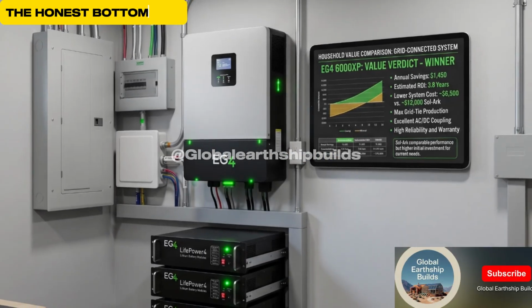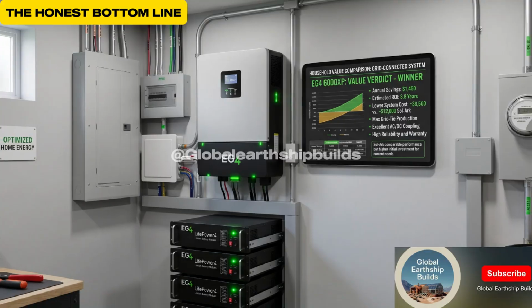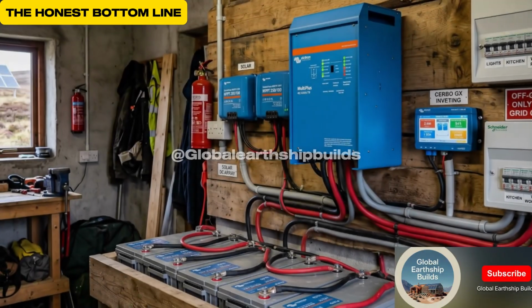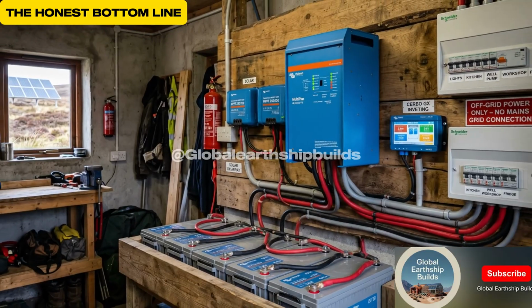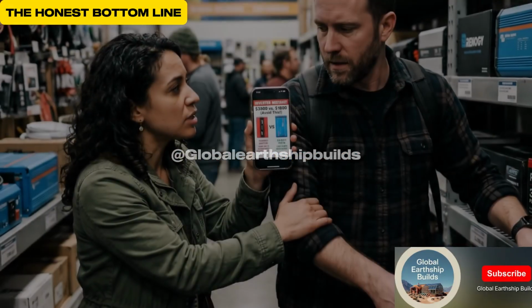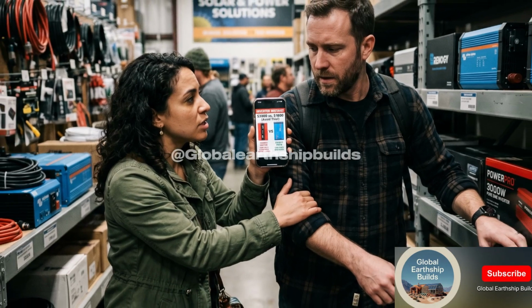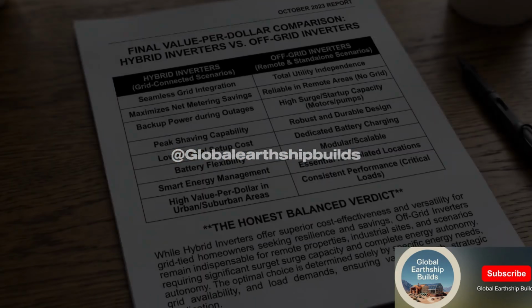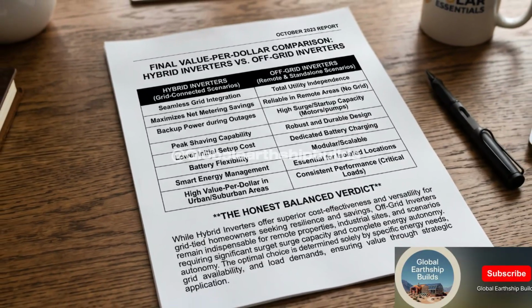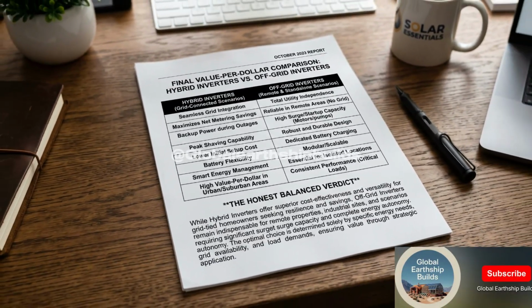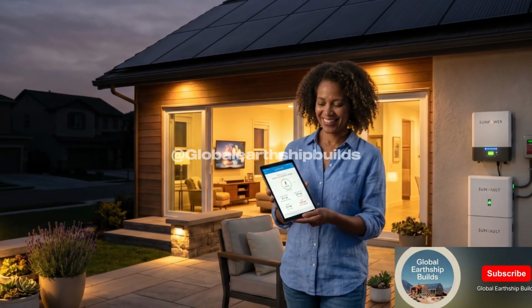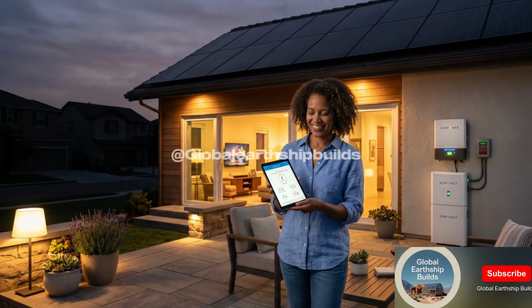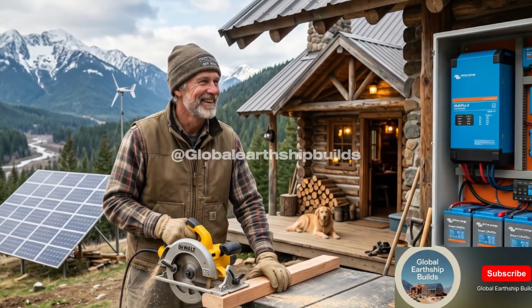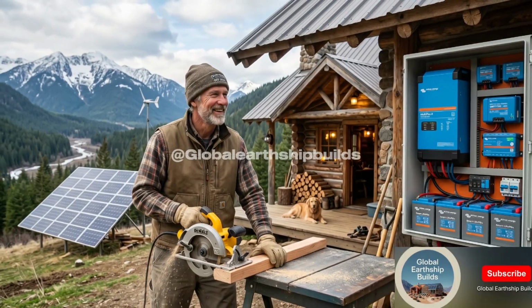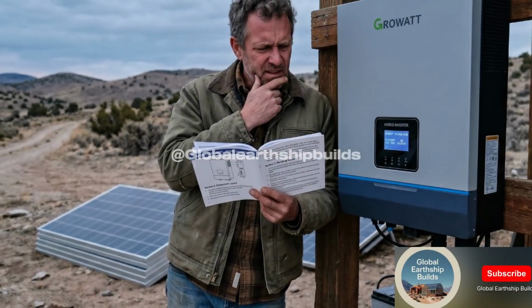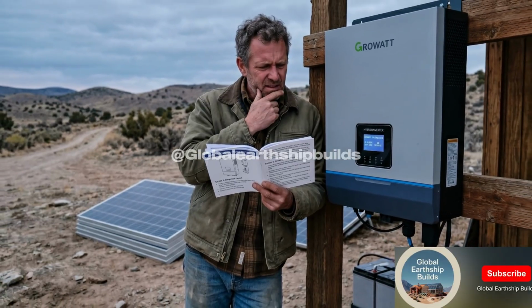The honest bottom line: the hybrid inverter wins on value for the dollar for the majority of people watching this video. If you have or expect to have grid access, the flexibility, the grid backup capability, the time of use optimization, and the reduced battery bank requirements make a modern hybrid inverter like the EG4 6000XP or Sol-Ark 15K a smarter financial choice than a dedicated off-grid unit in most scenarios in 2026. The off-grid inverter wins when the grid is not in the picture at all, when surge demands are extreme, or when total independence from the utility is the mission.